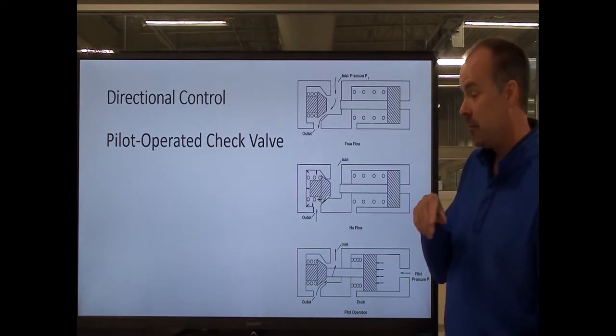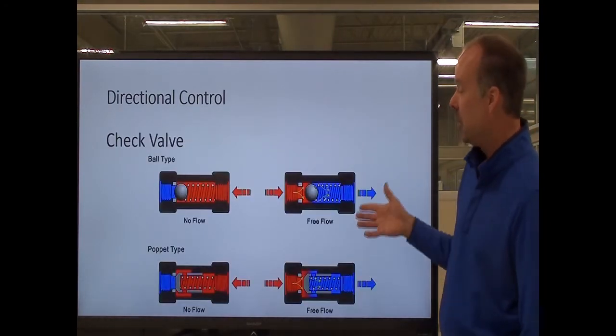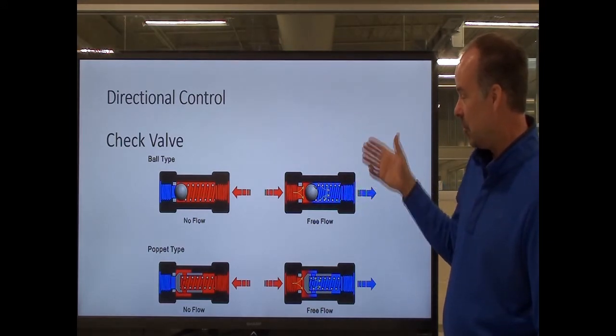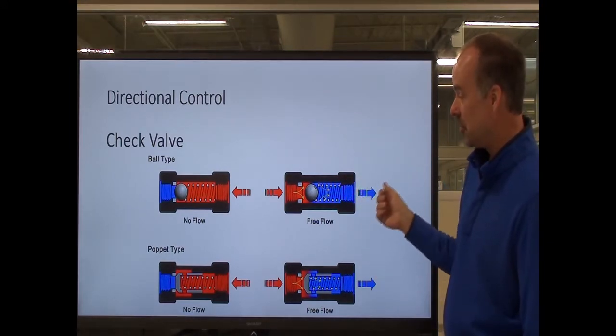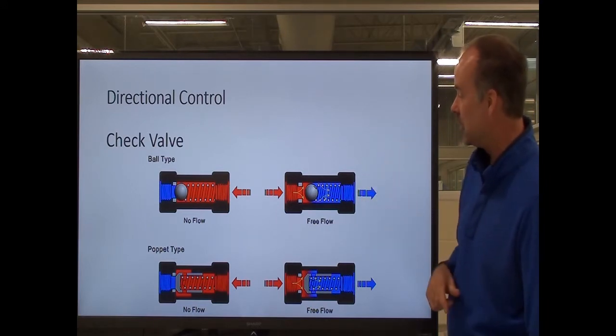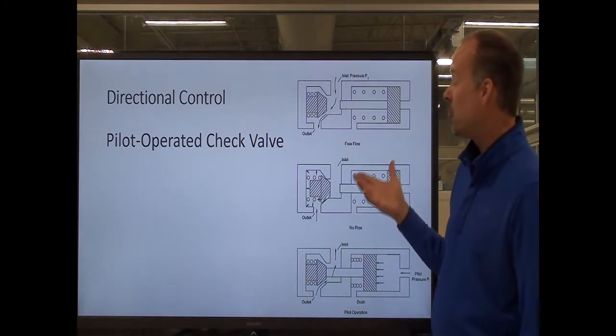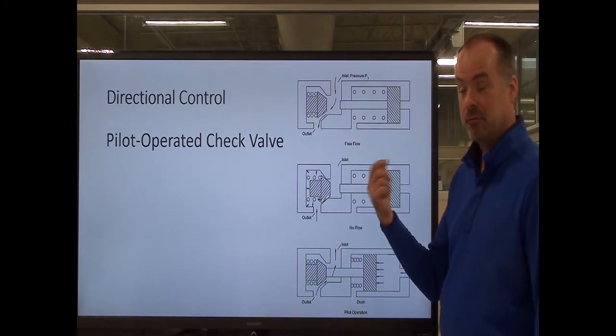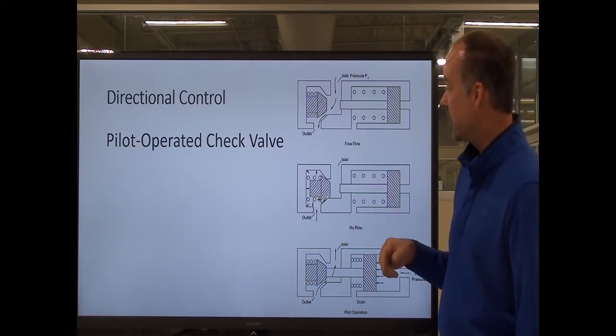Another type of check valve is the pilot-operated check valve. A standard check valve just allows the fluid to flow in one direction and seals it off in the other. A pilot-operated check valve has an override line that will actually allow fluid to flow in both directions when an override is activated.